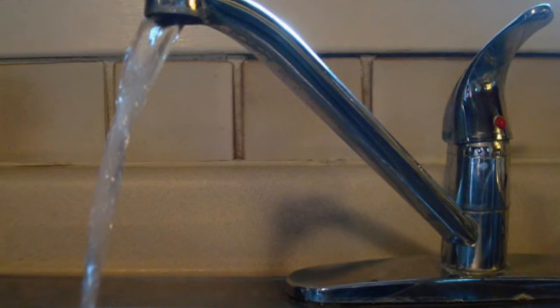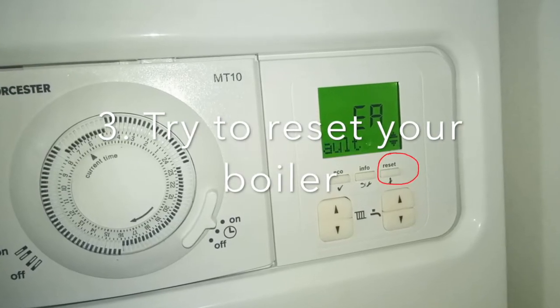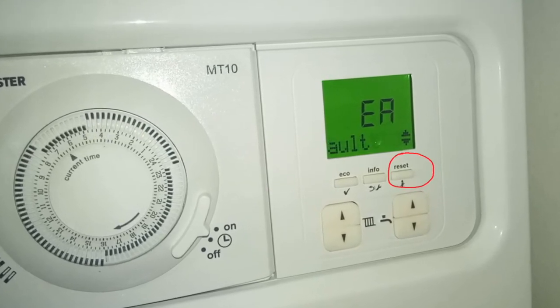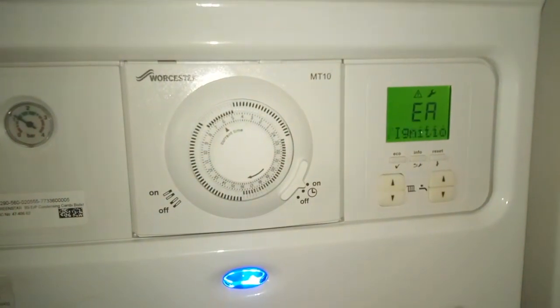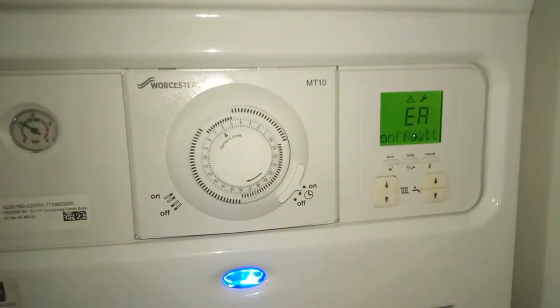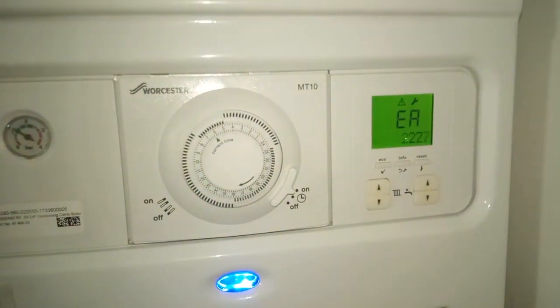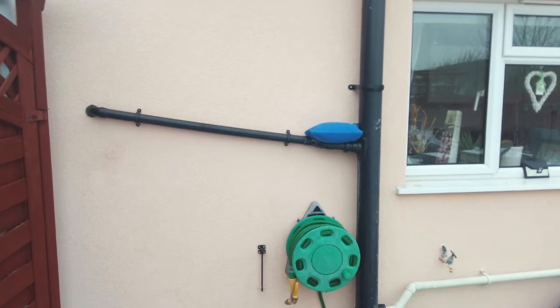Finally, turn the hot water tap on, click reset, and observe. Most trivial issues can be solved by simply resetting the boiler. Even after several resets, if the boiler doesn't fire, it could be down to frozen condensate pipes.